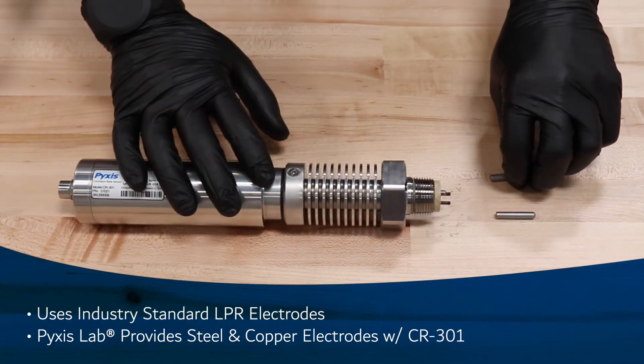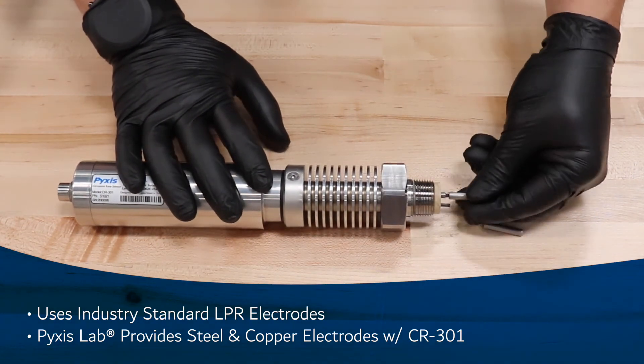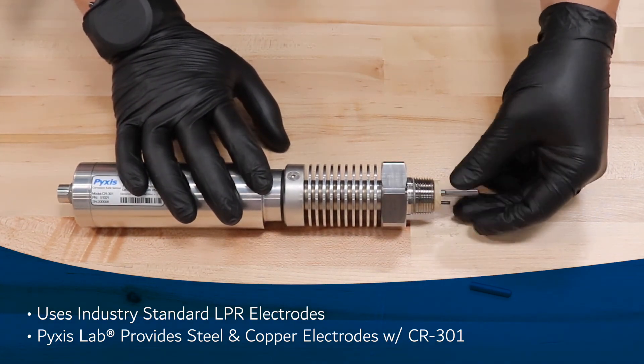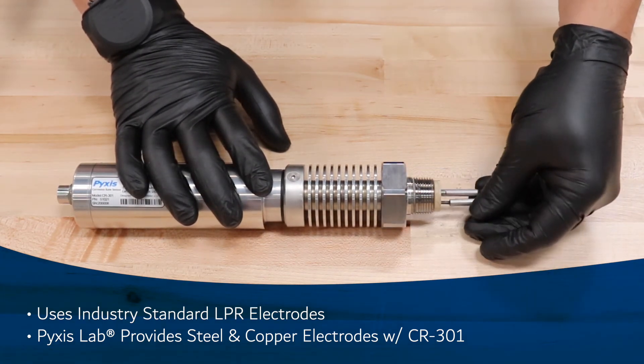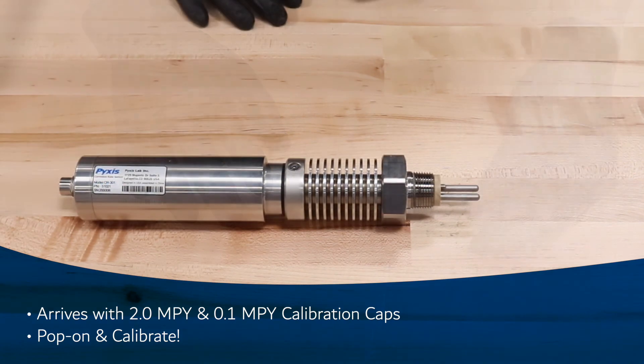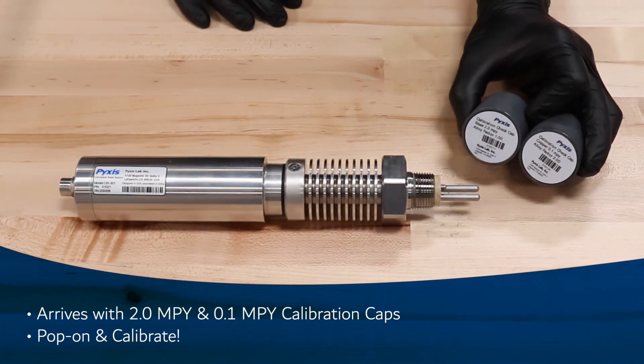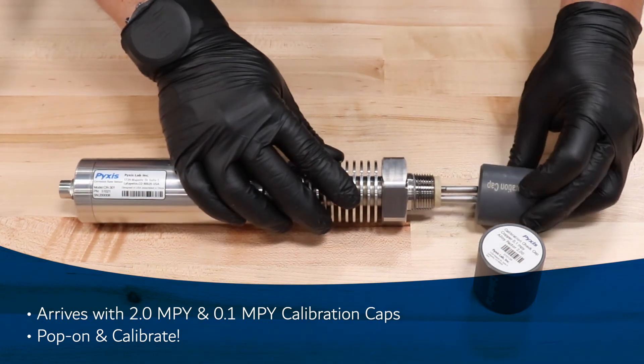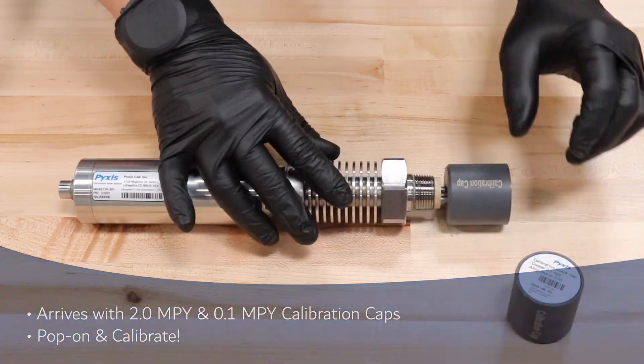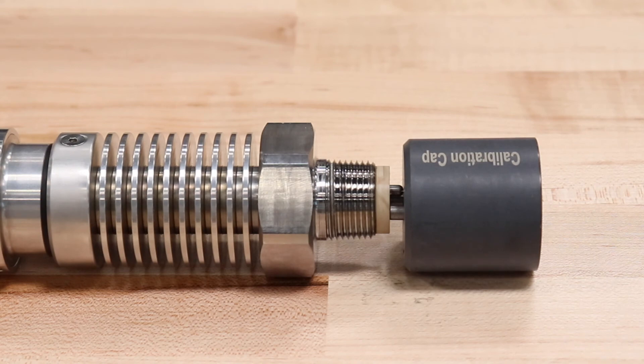The CR301 has been designed to utilize the industry standard LPR electrodes of 5 square centimeter surface area and 4-40 internal thread. Pyxis provides one set of steel and copper electrodes with the purchase of each CR301. Each CR301 is also shipped with a 2.0 mil per year and a 0.1 mil per year corrosion calibration reference cap. Simply install the calibration cap on the sensor electrodes and read live corrosion data on a connected controller to verify that the sensor has been configured and is performing as designed.